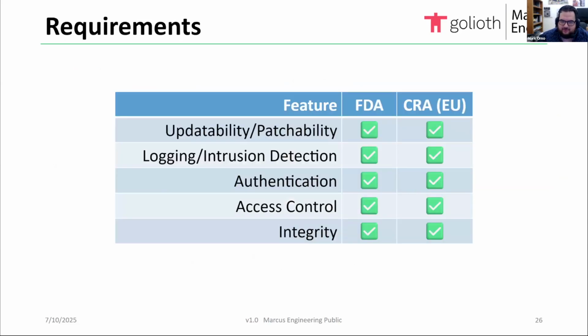And so I won't go through all their requirements, but it turns out they're actually extremely similar to the FDA's requirements, the CRA. They require a couple of things like secure by default. It has to ship in a configuration that is secure, and it has to be able to have those reset functions. It has to have access control, encryption, integrity, all the same stuff. They require you to limit the attack surface specifically. And they also require auto updates, slightly more strong than the FDA. And they also require you to have strong, clear mechanisms to disable those updates as well.